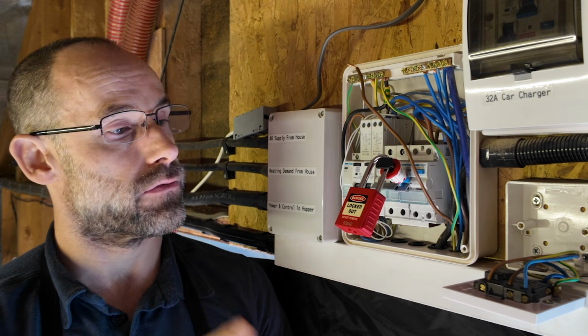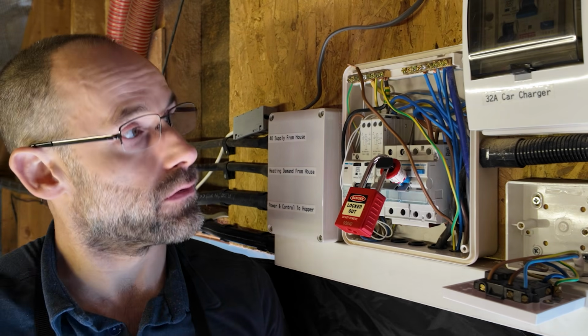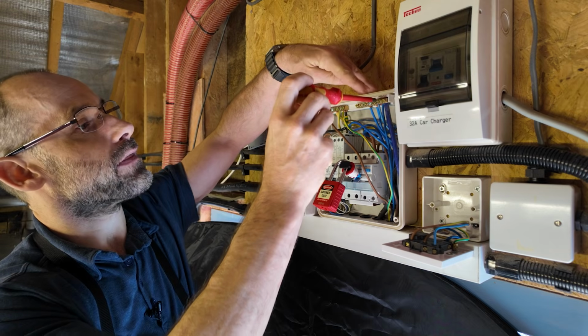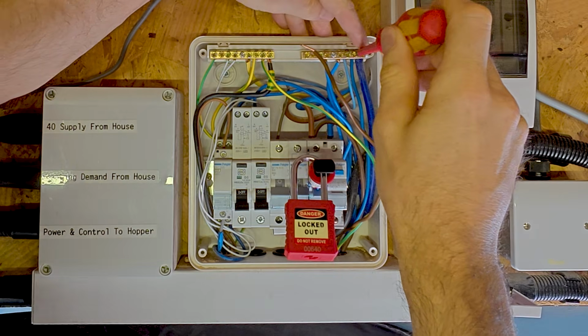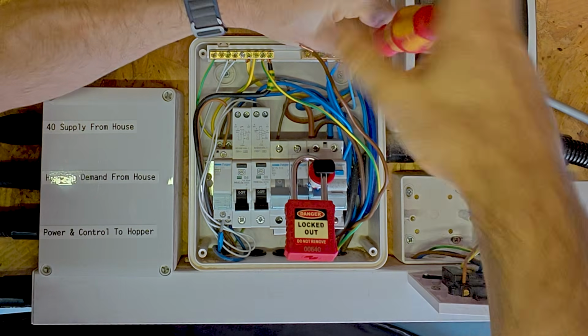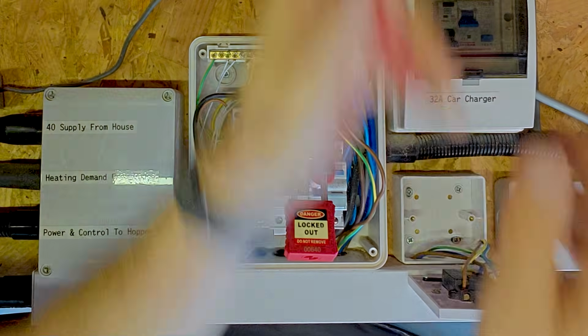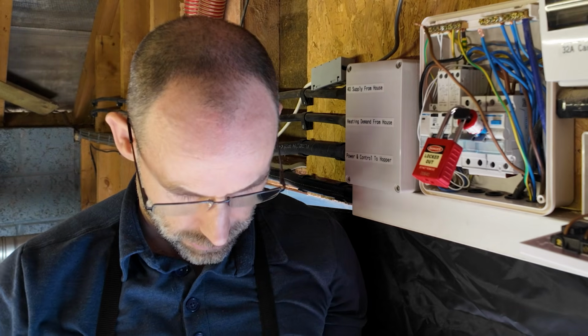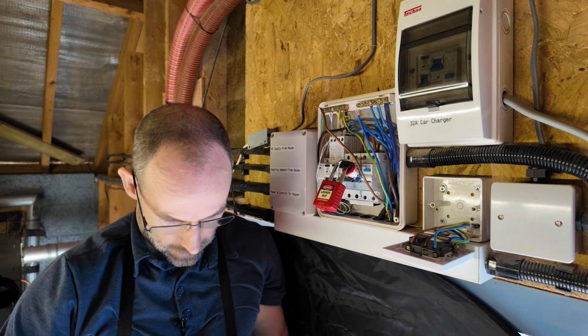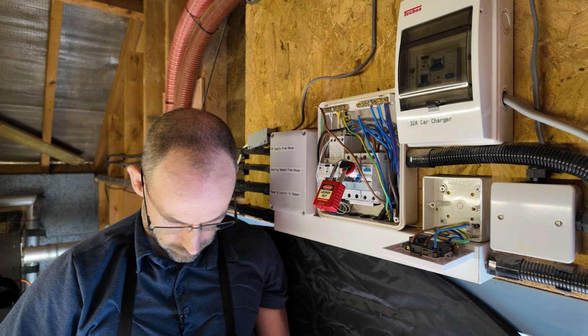Now we've got 3 sets of insulation resistance tests to do. It's a bit like when we check things are dead, we check between all three possibilities. Imagine my three conductors laid out in a triangle. The blue one, the brown one, and the yellow and green one. And you can imagine that there are three sides to that triangle, therefore three combinations that we need to test. So you need a special device for this. This is why we leave this job to electricians.